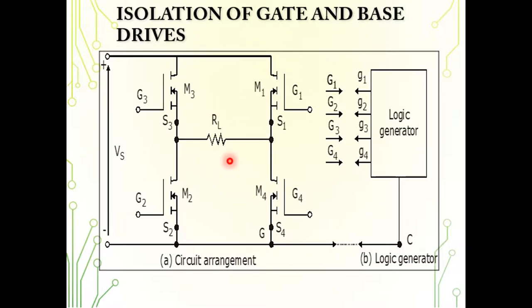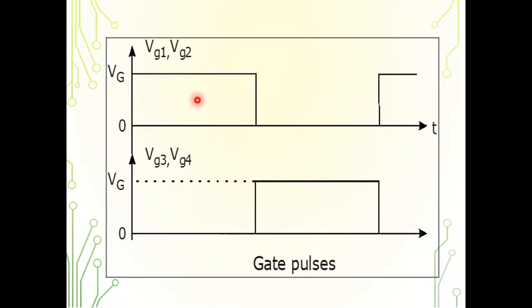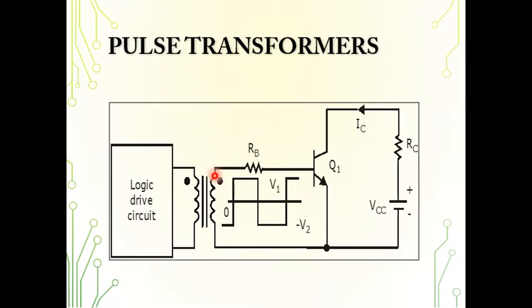This inverter circuit carries large power, whereas the logic circuit which generates the gate or base drive pulses carries very low power. We obviously need isolation between this logic circuit and the power circuit. One way of achieving this isolation is by using a pulse transformer. The gate pulse generated from the logic circuit is applied to the primary of the pulse transformer, and the output is taken from the secondary.